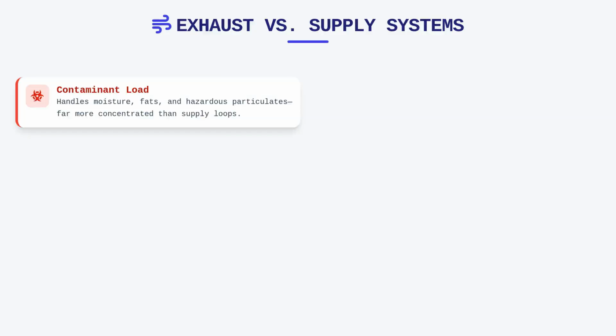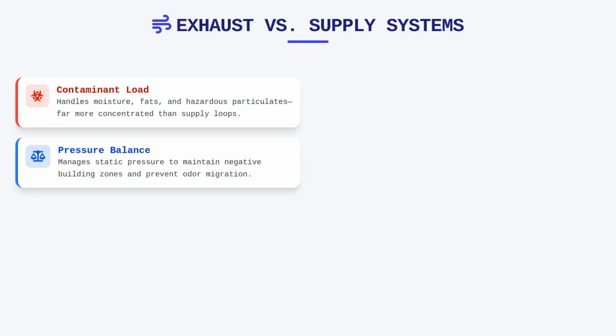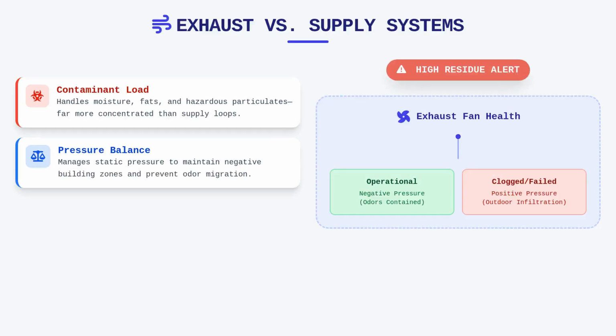Exhaust systems differ significantly from supply air systems because they often handle air laden with contaminants, moisture, or fats that would be unacceptable in a standard HVAC delivery loop. When we talk about general exhaust, we are often managing static pressure that directly influences the pressure balance of the entire building. If a building is meant to be under negative pressure to prevent odors from migrating, a failure in the exhaust fan or a clogged riser can flip that balance, leading to unintended infiltration of outdoor air.